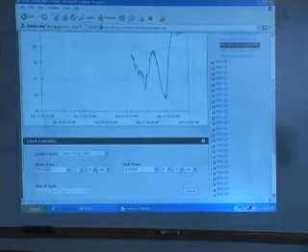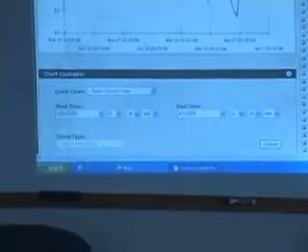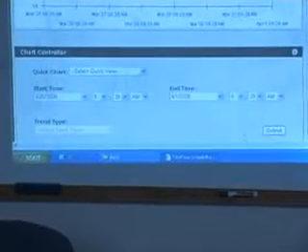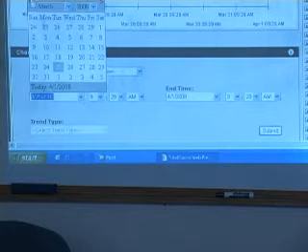This site we just turned on a few days ago, so we don't have that much historical data, but in most of our projects, and this isn't specific to one manufacturer, most all control manufacturers' equipment has these features in one form or another. You can go back months and in fact years, just trend data for long periods of time and analyze it. You could plot a whole year's worth of data on one graph just to see what it looked like, or a week's worth to see that the building's going occupied and unoccupied as it should.